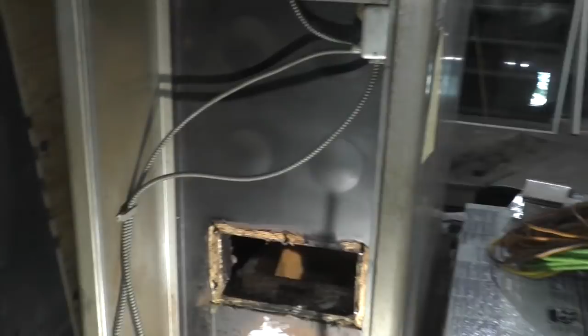Yeah, so what that's going to do is cause it to over temp. So when it's on a heat cycle, burner's running, thermostat's calling for heat, and it shuts down. Then it kicks back on again, and then it shuts down. Kicks back on, until the heat cycle or the demand is cut, thermostat satisfied, everybody's happy. So what that's doing is it's causing a restriction of gas from flowing through the furnace and out the chimney. It causes excessive heat in the upper part of the combustion chamber area. And what that's going to do, two things.